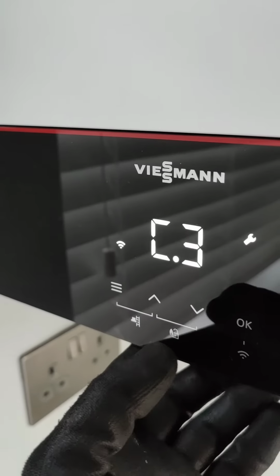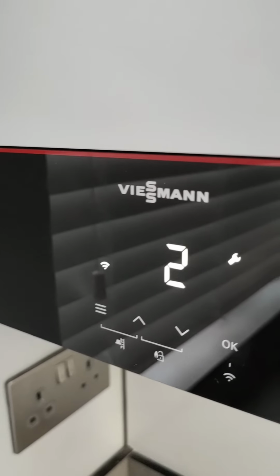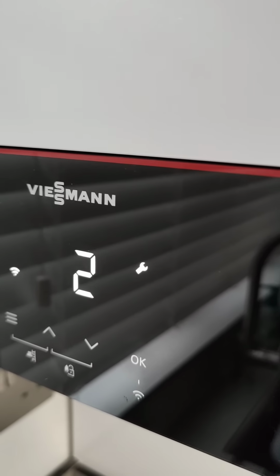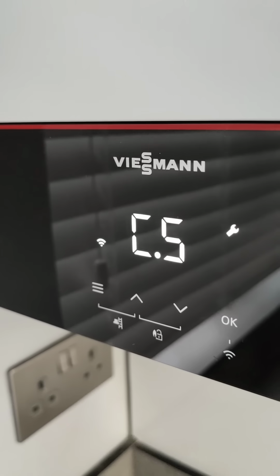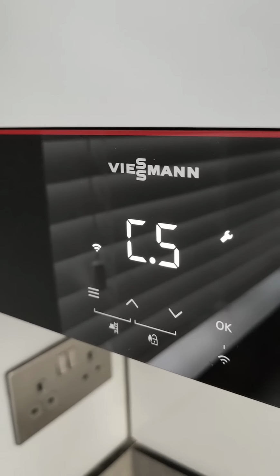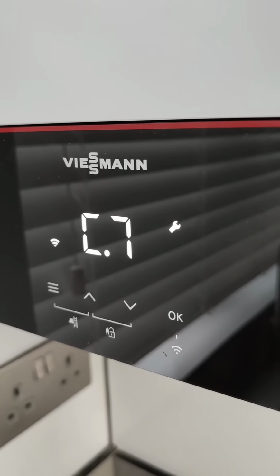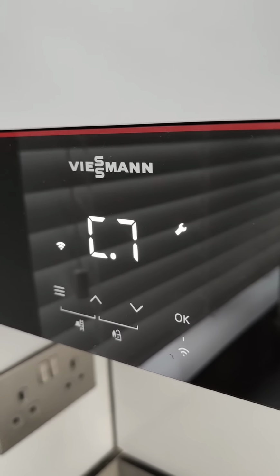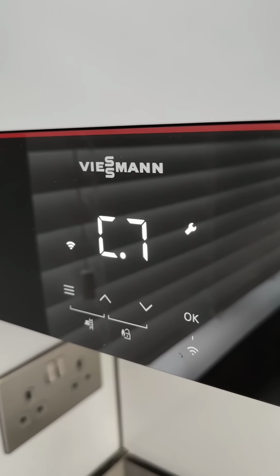So C3 is whether we've got natural gas or LPG. So number 2 is natural gas. C5 is the type of flue we've got. C6 is the length of the flue in meters. Now C7 is how we want the boiler to work for the heating. So whether we want to run it using the weather comp and the onboard computer, or whether we want to use external control, or whether we want to use weather comp with the external control.